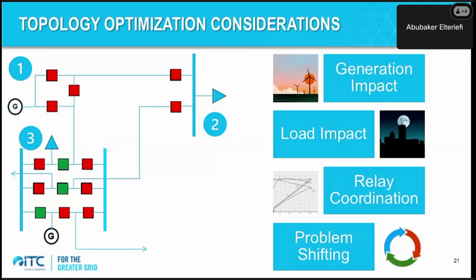You reroute the flow that way, possibly putting that load on radial. That's something you've got to watch for here. A more complicated network might move the problem elsewhere, but as I said earlier, we've seen a lot of good applications there as long as we do the review ahead of time and coordinate with impacted parties. It's shown very good results.